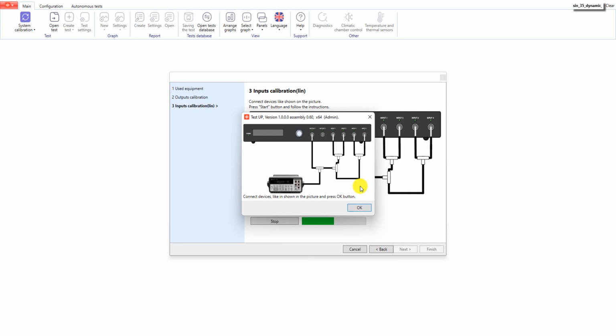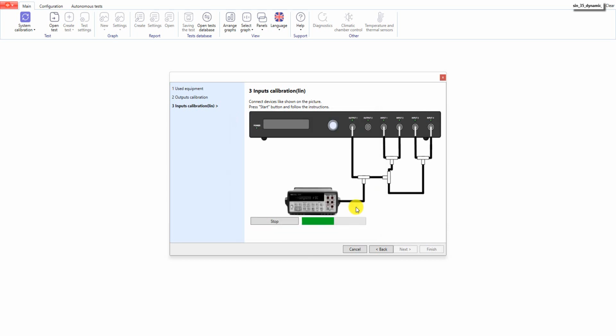We connect all the devices as shown in the picture and press start. This step is also done for all the outputs. After all these steps are done, our device is recalibrated and its accuracy will increase. This way you can verify and calibrate your vibration controller.